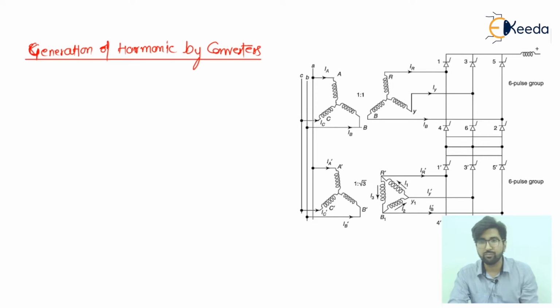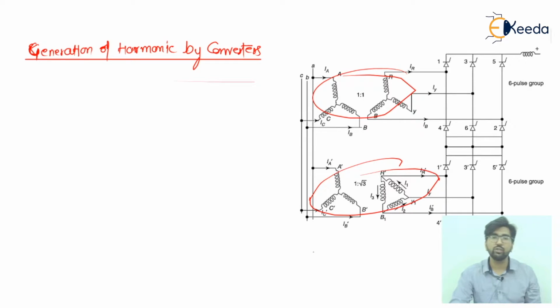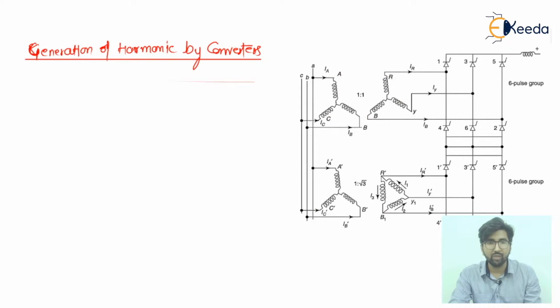In the first set of operation, it is having 1:1 ratio, and here 1:√3 ratio. The first is actually connected into star and star connection, and the second is connected in star and delta connection. So likewise these are connected, and we have discussed this in the second chapter. This is the first 6 pulse group, and this is the second 6 pulse group.